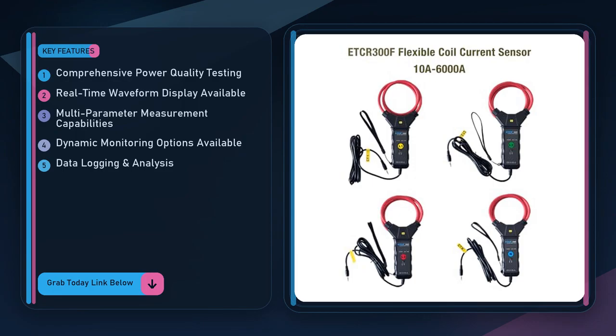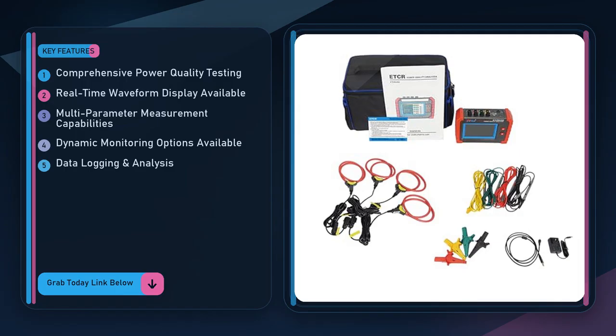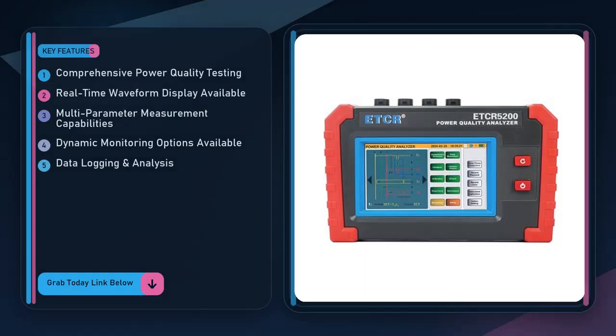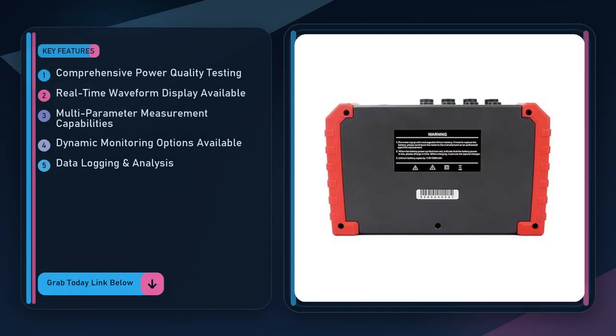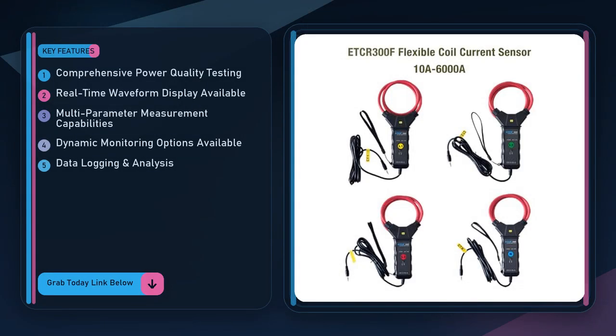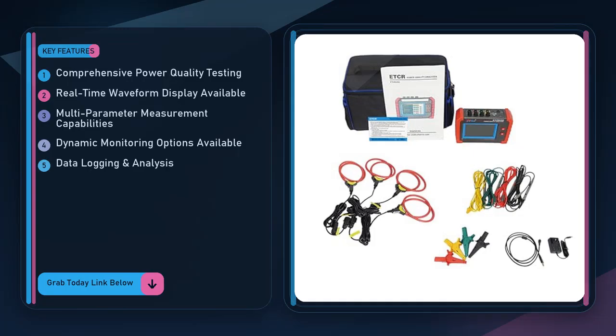Imagine you run a small manufacturing line that uses 3-phase motors, variable frequency drives, and a mix of LED lighting. You've noticed occasional trips on your main breaker and suspect power quality issues, but you've never had a way to see what's happening on the line in real time. The ETCR5200 plugs into a single phase of your supply, the clamp slips around a line conductor, and the unit starts displaying waveforms, phasor angles, and harmonic distortion right on its screen.